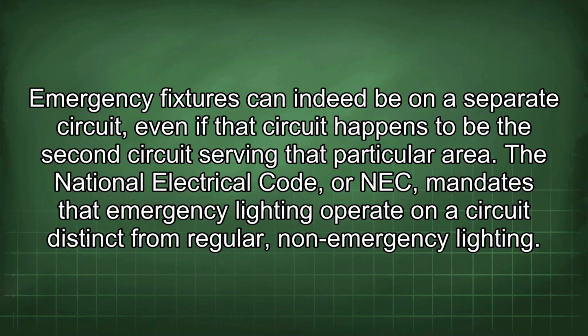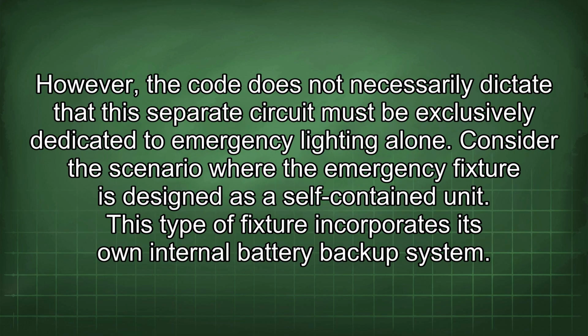Emergency fixtures can indeed be on a separate circuit, even if that circuit happens to be the second circuit serving that particular area. The National Electrical Code, or NEC, mandates that emergency lighting operate on a circuit distinct from regular, non-emergency lighting. However, the code does not necessarily dictate that this separate circuit must be exclusively dedicated to emergency lighting alone. Consider the scenario where the emergency fixture is designed as a self-contained unit.